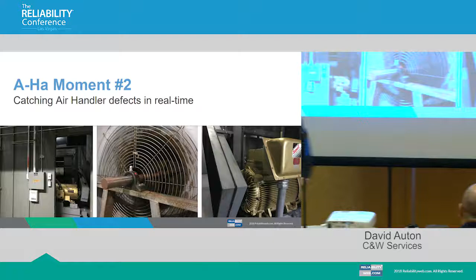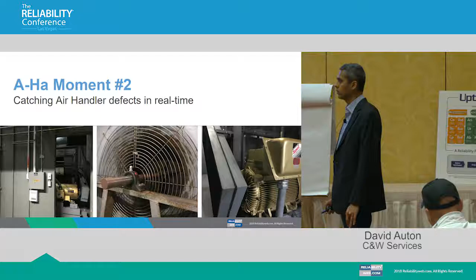And you did have a case before we showed up, right? Yeah, that was one of the reasons we moved with this—we'd had a couple of scenarios of failures like that, even though the guys were lubricating them with the correct frequency. We had one where they did the sampling and caught it early on, but the other one failed. By the time we were able to detect it—because again, that's in a sealed chamber, and you have to do lockout tagout to go in there—by the time we found it, we had to replace the shaft and the pillow block, and that cost more than our entire pilot.